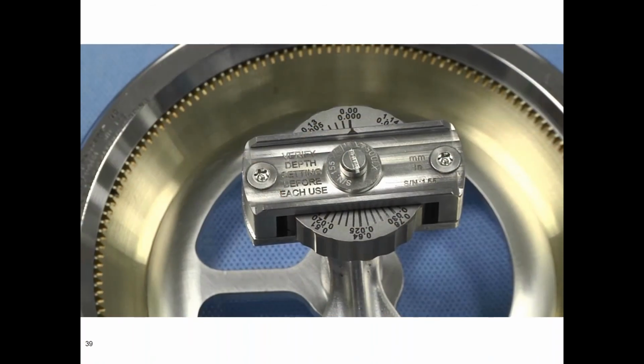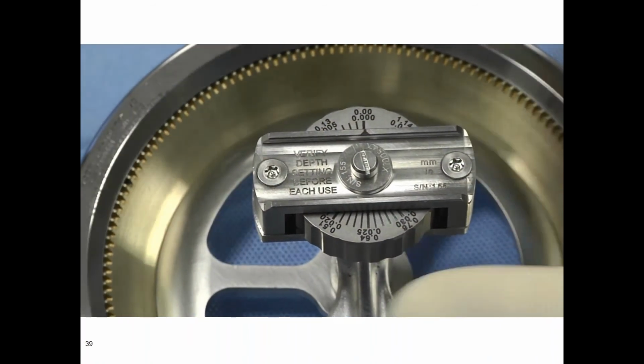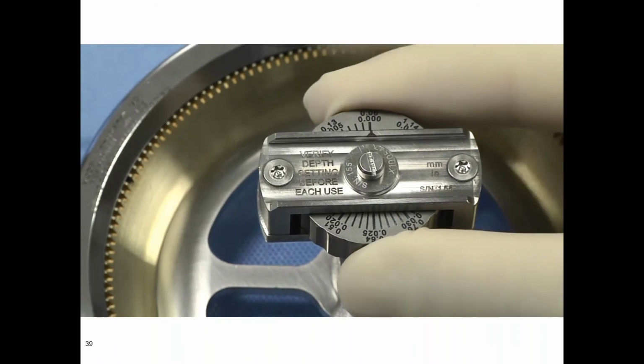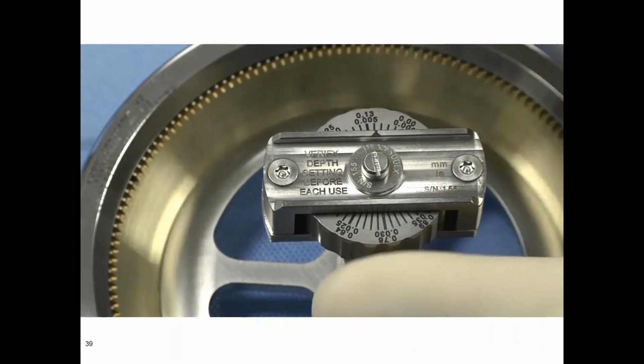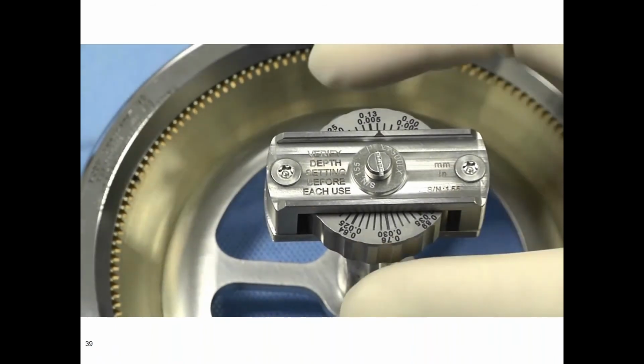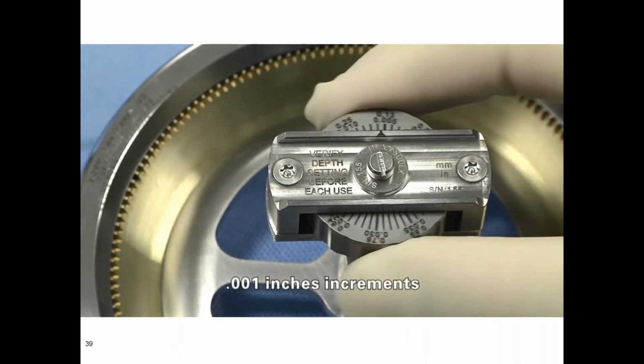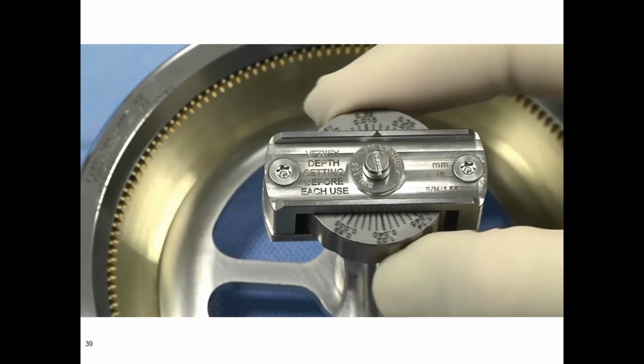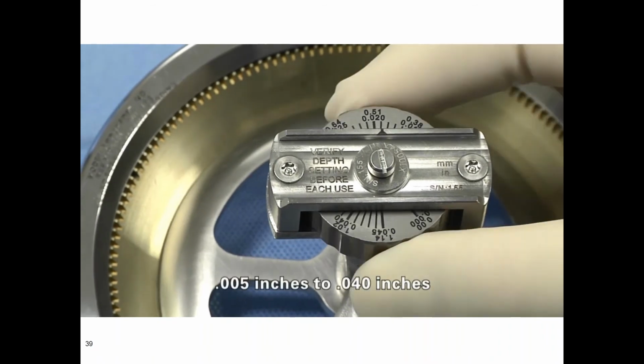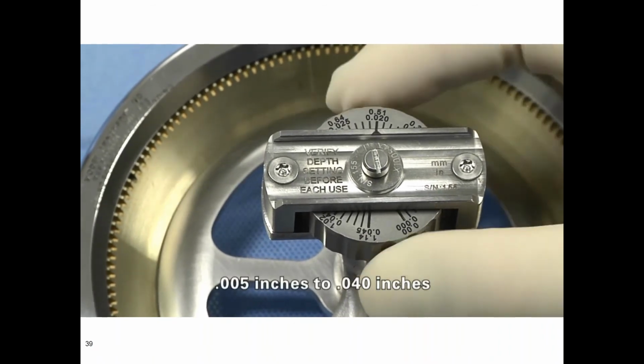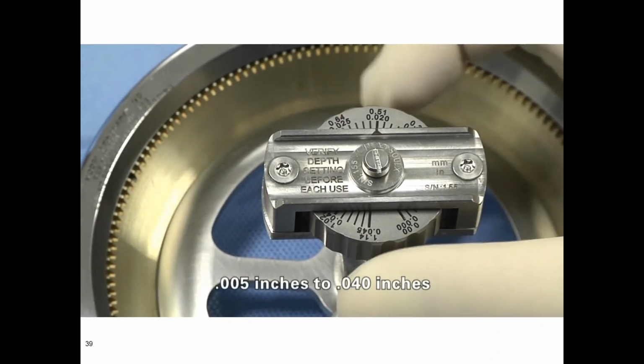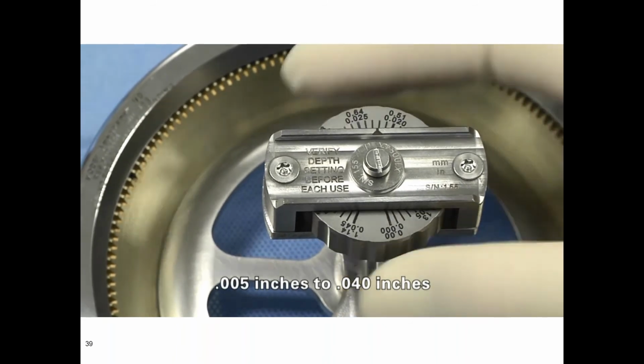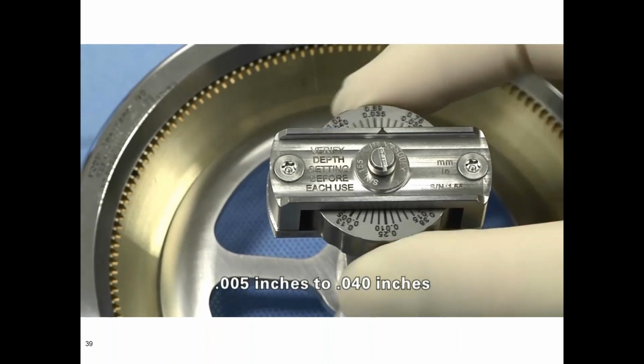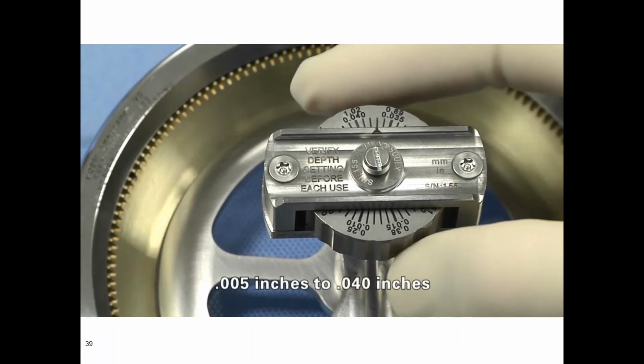Adjust depth settings to the desired thickness by turning the depth adjustment knob. Settings on the depth adjustment knob indicate increments of 1 thousandths of an inch and will cover a range of 5 thousandths of an inch to 40 thousandths of an inch. Note, the depth settings are a guide, and the resulting skin graft will depend on donor demographics and processor protocols.